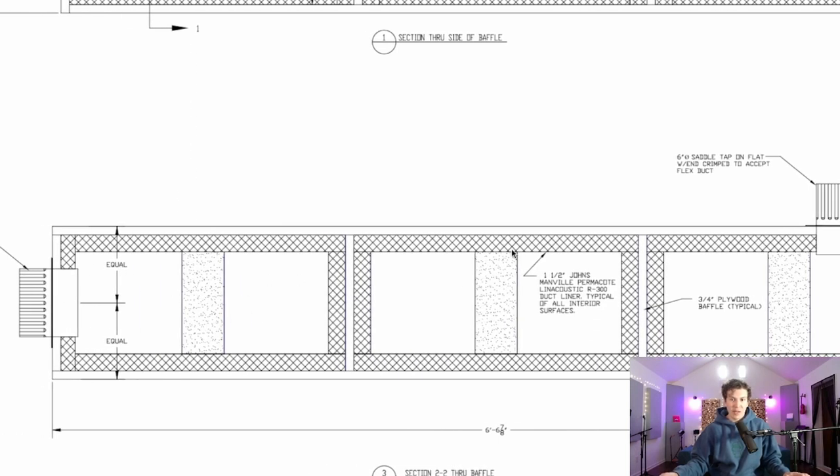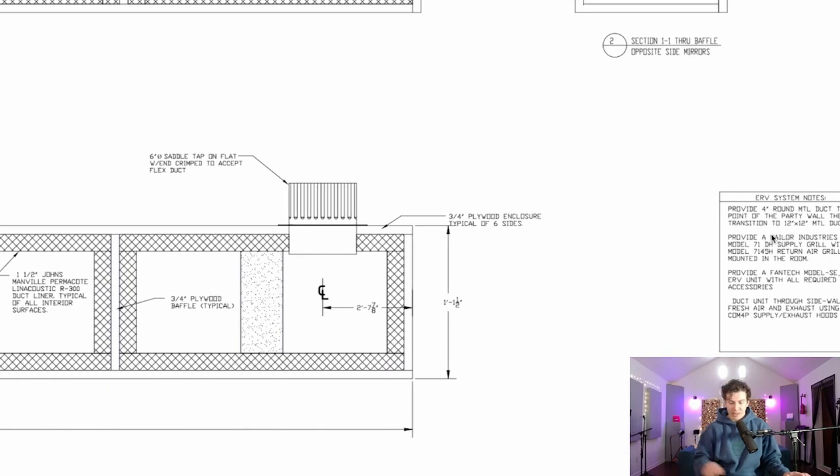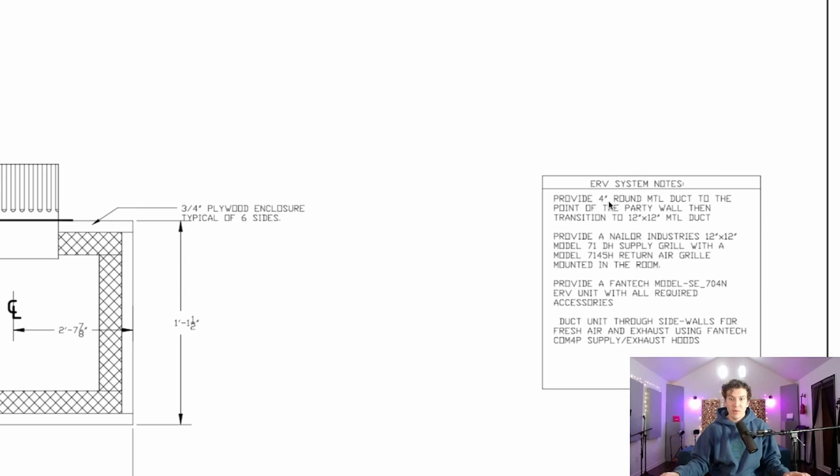Here's a side view, and here are the system notes. Provide a four-inch round metal duct to the point of the party wall — the wall between your mechanical room and your actual studio — and then it transitions to the 12-by-12-inch duct going into the studio. You want to buy the Nailor Industries 12-by-12 Model 71 DH supply grill with a Model 7145H return air grill mounted in the room. These are special order, so give yourself enough time; a lot of providers won't have them on hand.